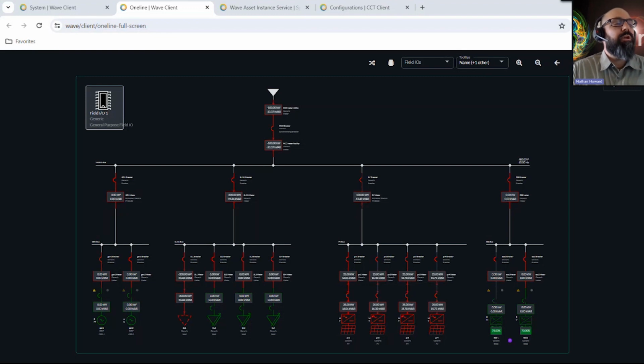The other consideration is that Wave has the ability to understand when assets are in a local or remote control state, where the asset might need to be manually operated from the faceplate or is in a maintenance state, and so should not be part of the typical operation. In that situation, Wave won't take advantage of those assets. It'll still show them on the one line. It will still monitor them, but it won't use those. It looks like maybe those loads are still in that state in the emulator, so Wave won't be bringing those online for us today.